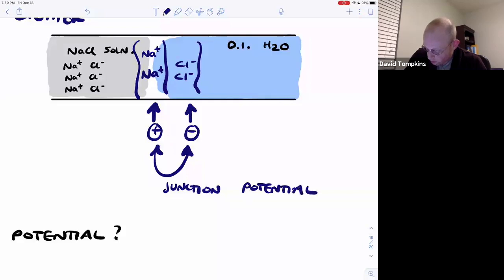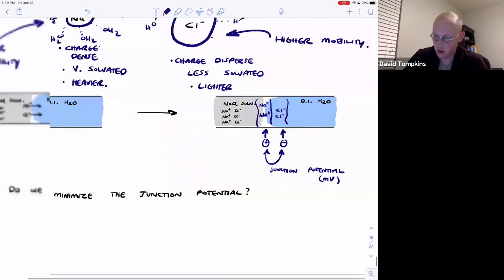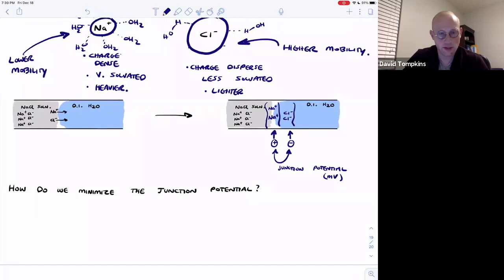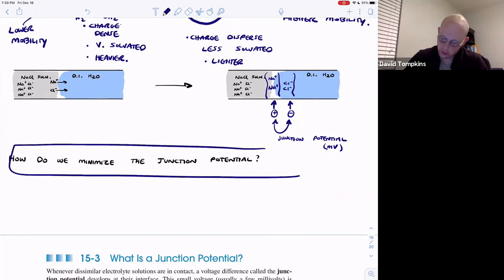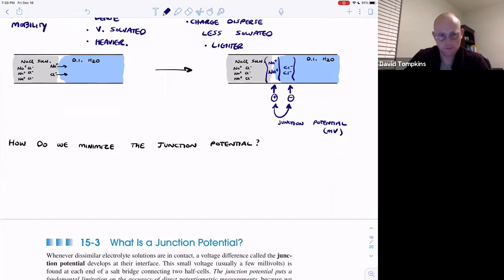That's usually a few millivolts as I mentioned, but it's going to cause inaccuracies for your measurement of concentration for the electrolytes that you do care about measuring the concentration of. So we ideally want to minimize this junction potential. It's impossible to really make it zero, but we can minimize it by using potassium chloride.